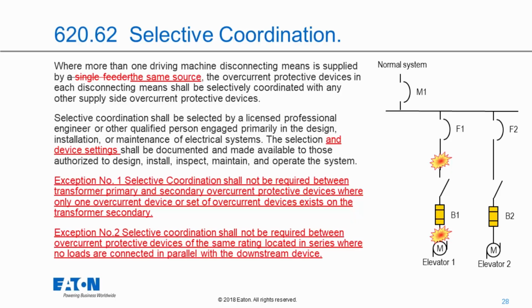So the reason why they changed it to the same source is many would argue that the scenario I have right here, where I have the main and two feeders, each feeder supplying an individual elevator, is not supplied by a single feeder. They would think that M1 is not considered a feeder, and that is not the case. M1 would be considered a feeder. It might be the service main, but it also is a feeder. Now, granted, there are special requirements for that because it is the service main, but essentially it supplies both elevators.